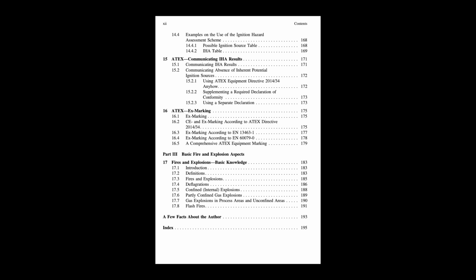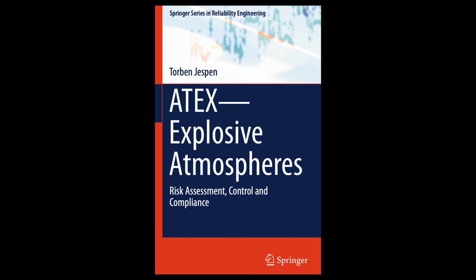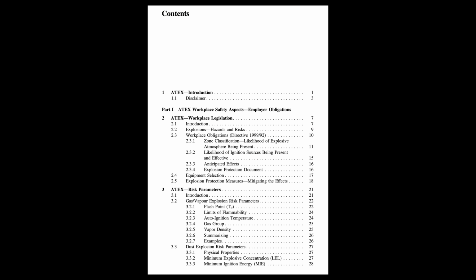The final category assigned to the whole piece of equipment is determined by the single ignition source that requires the highest level of protection, i.e. the lowest category number. If even one potential source could become effective in normal operation, it likely needs to be Category 1 equipment. And the IHA might also specify usage restrictions. Yes, very often. Things like maximum ambient temperature, suitability for specific gas groups or dust types, maybe limits on speed or load. These restrictions must become part of the equipment's marking and instructions for use. The IHA report itself is a crucial part of the legally required technical documentation for ATEX equipment.